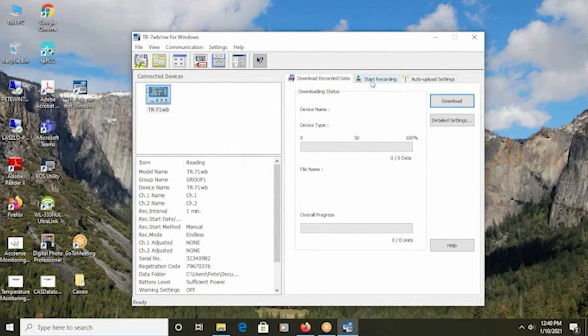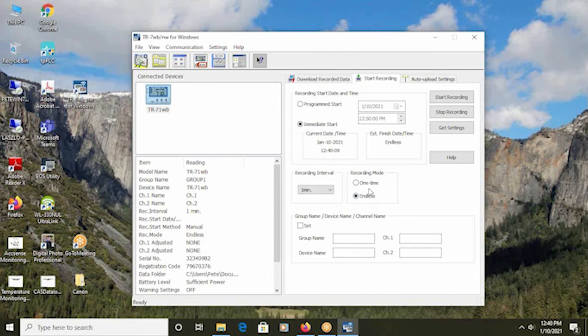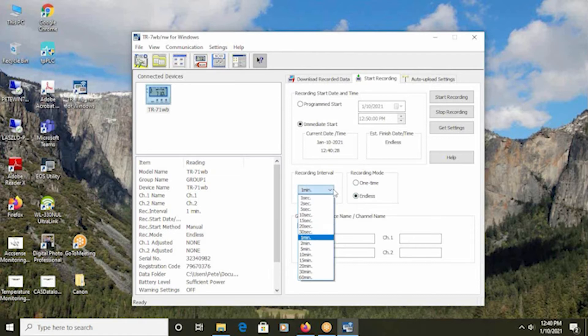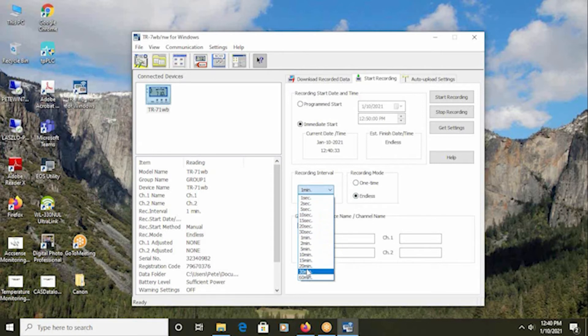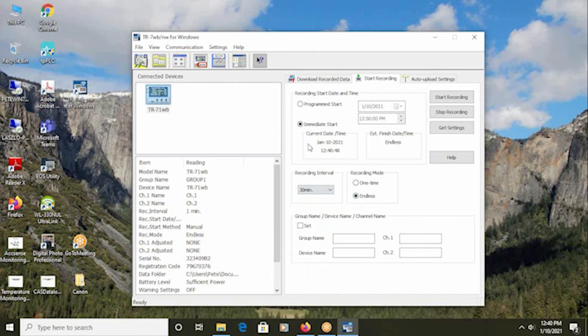Once you have this open and you have the device showing up in the window, go to the Start Recording tab. Here's where you enter the recording mode. Most customers should choose Endless so that the logger will record the data in a circular buffer fashion, meaning after the first 16,000 readings are recorded, it will start overriding and log record onto the older readings so that you always have a continuous package of data. The typical recording interval that most customers would use would be 15 or 30 minutes, meaning that the logger will take a sample and store the data every 15 minutes or every 30 minutes. That is usually very sufficient for the typical refrigerator or freezer monitoring application. Immediate start is the expected way to go so that the minute you stop the configuration, the recording will begin.